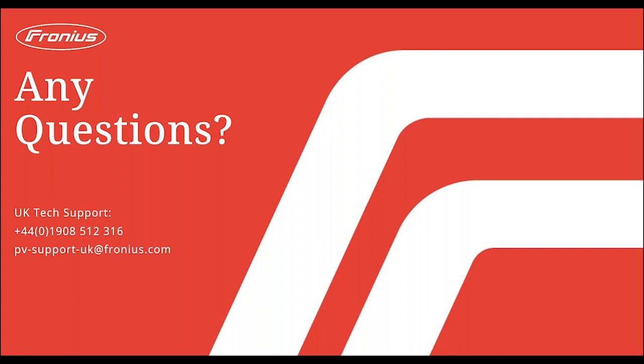That's from Ian. So the two Gen24s will operate independently if you have them on the same system. With the software updates, you'll be able to use one as the leader with export limitation, but in terms of battery charging, it will only be one that will charge the battery. You can't have two battery connected devices. But the good news is the second inverter, which doesn't have a battery, can still feed its surplus energy to the main Gen24. And this is done through AC coupling. There's no hardware changes required. It's simply a case that the battery-enabled inverter draws in surplus energy, looking at the smart meter readings. So we can do everything with the system except for power a second battery from a second inverter.